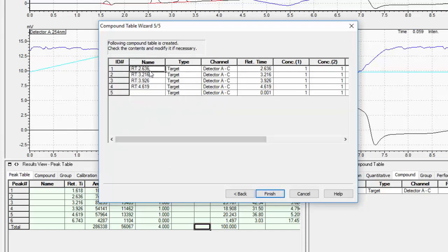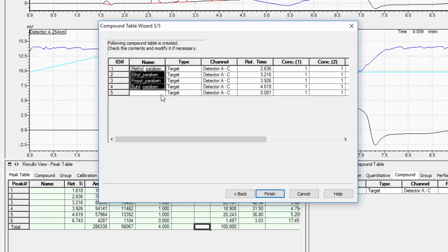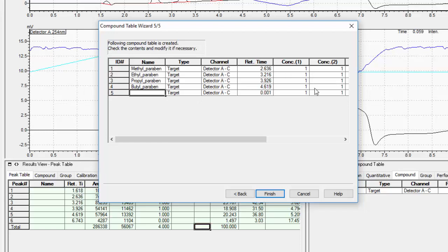Finally, when you click next, you will be presented with the compound table you have created. Your peaks of interest you selected will be auto-named based on their retention times. You can go in and manually change them to reflect the names you wish to identify them as. By default, each one of your peaks will be identified as a target. If a given peak represents an internal standard or a reference, you will need to select that from the drop down menu of the sample type here. Additionally, if you entered any information regarding the quantitative method and the number of levels, you will have an opportunity to enter in the concentrations for each of the levels you specified.